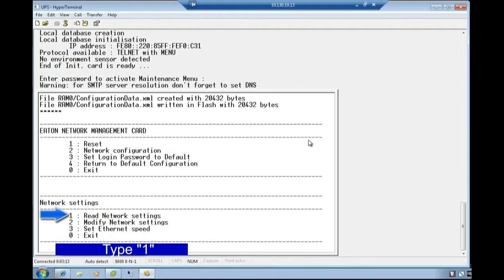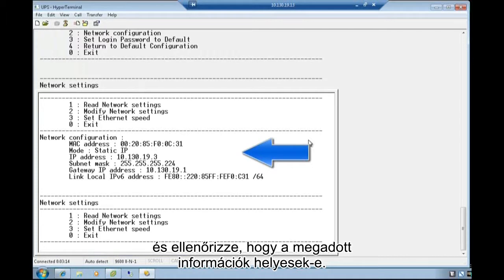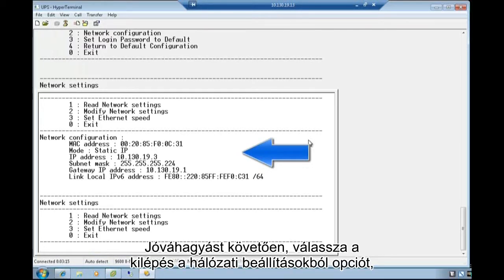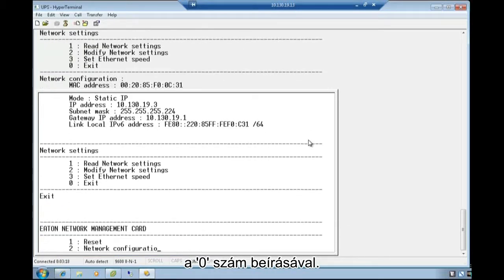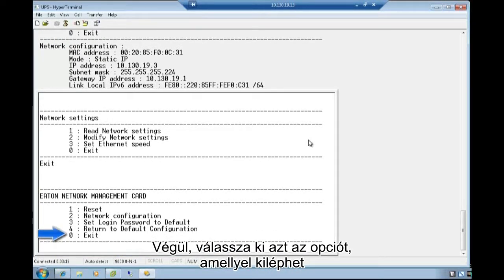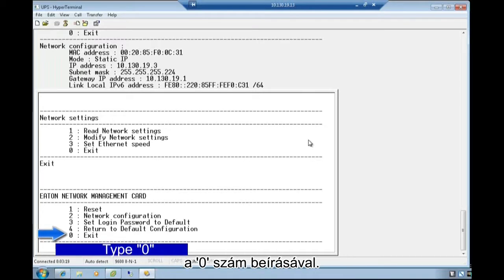Type the number 1 and verify that the provided information is correct. Once confirmed, select the option to exit network settings by typing the digit 0. Lastly, choose the option to exit from the Eaton Network Management card by typing the digit 0.